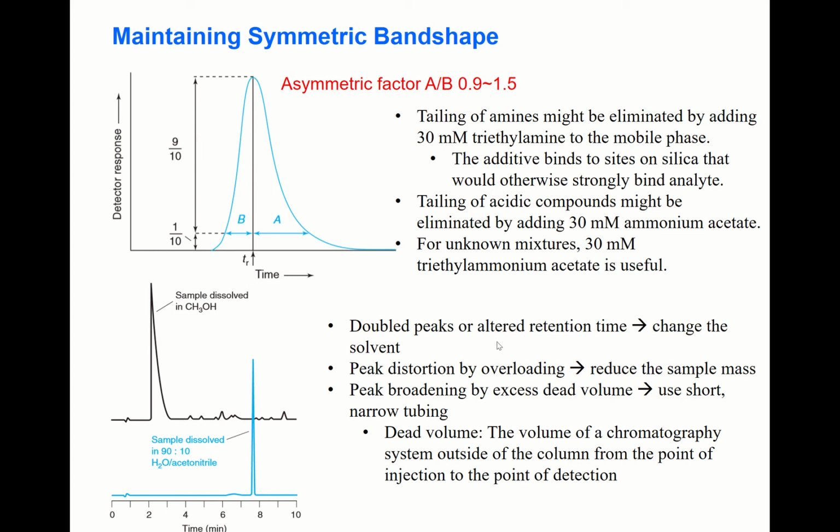Double peaks or altered retention time, when this is observed, change the solvent. This one is quite bad actually. Peak distortion by overloading: if you inject too much sample, peak distortion may occur. In this case, reduce the sample mass.